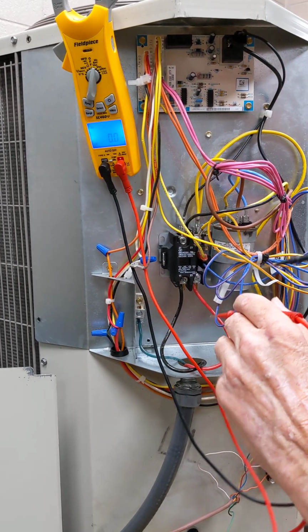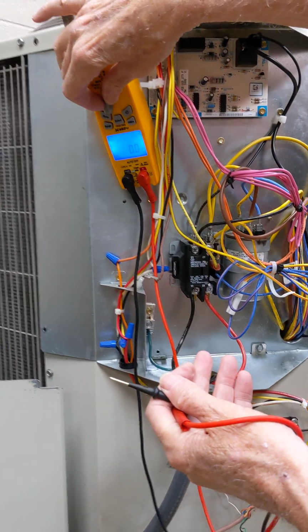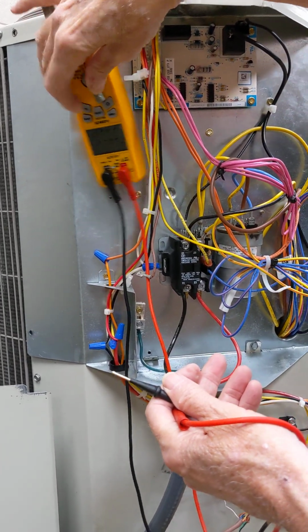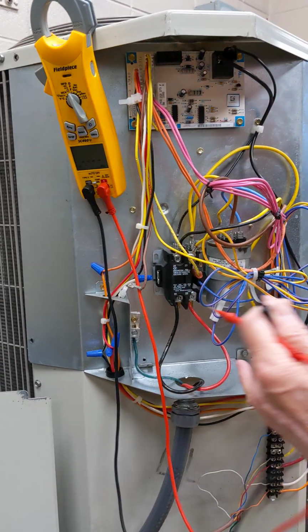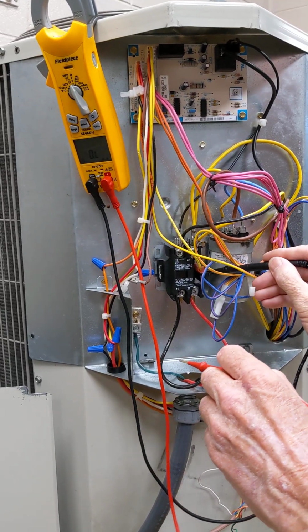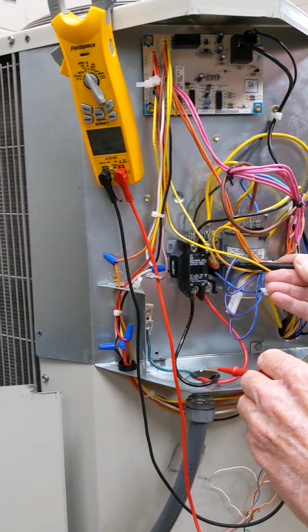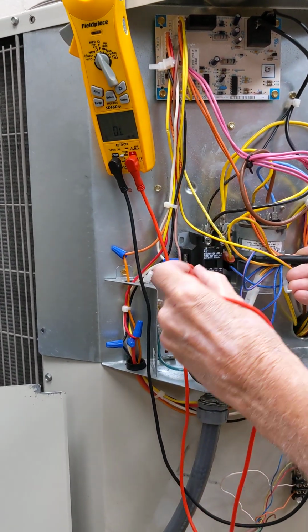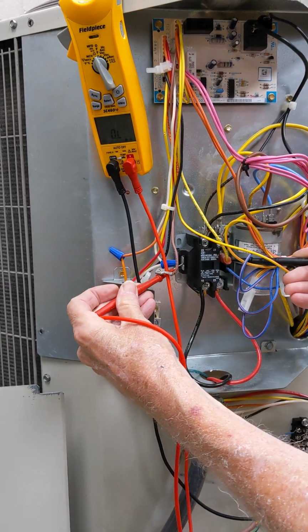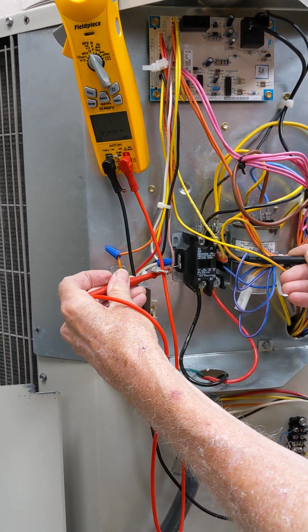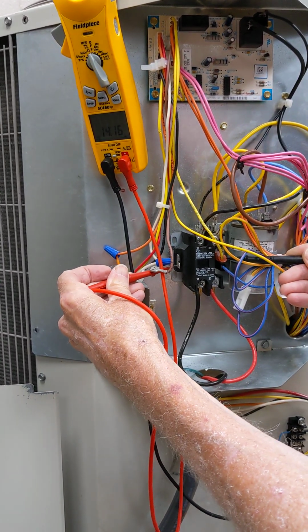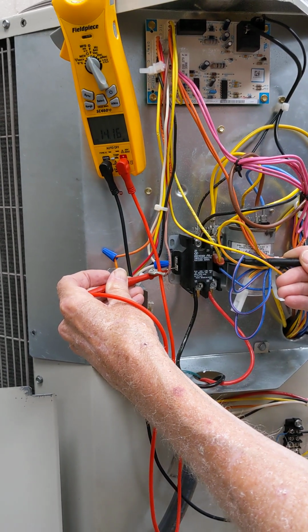So this is the last thing. I'm going to check the low voltage coil with ohms. So I'm on the metal on this one. I've disconnected one side to make sure the meter is only reading through the coil. And I got, looks like 14.15 or something like that from here. I can barely see the meter, okay?